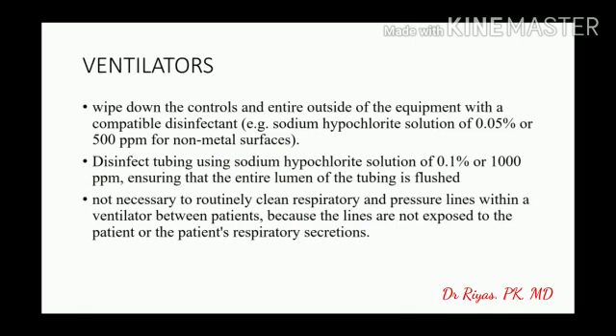Wipe down the controls and entire outside of the ventilators with a compatible disinfectant as advised by the manufacturer. Disinfection of tubings is done as described earlier, and it is not necessary to routinely clean respiratory and pressure lines within a ventilator between patients because the lines are not exposed to the patient or the patient's respiratory secretions. Bacterial or viral filters also may be used at the expiratory end.